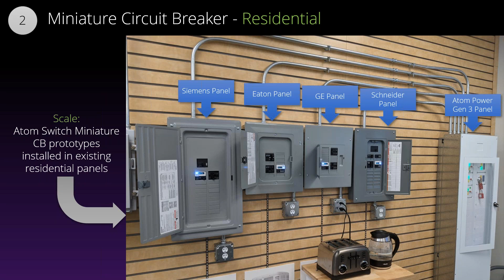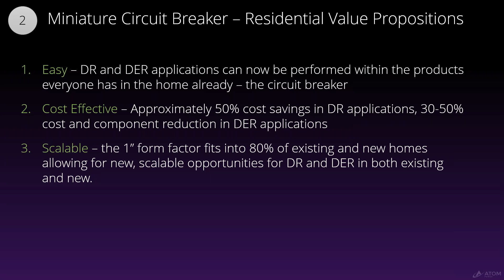The reason for this is that our miniature circuit breaker's demand response and distributed energy resource applications are growing faster than ever, and we can enable that with just a breaker replacement in the load center. It's cost effective, cheaper than putting in additional panels and contactor or relay based solutions, and it's scalable with the 1-inch form factor.